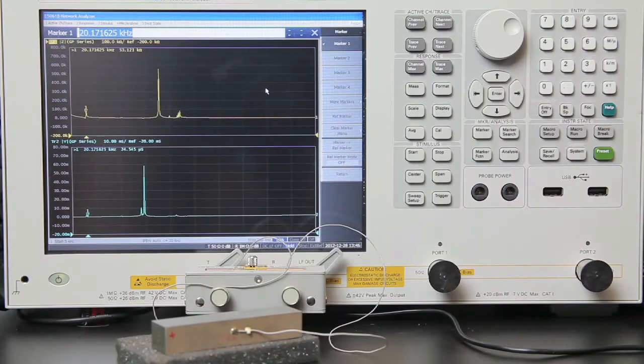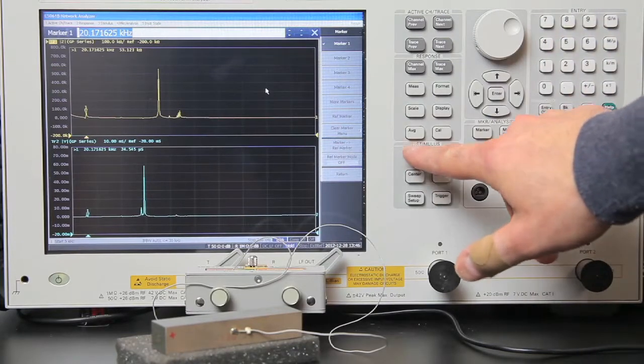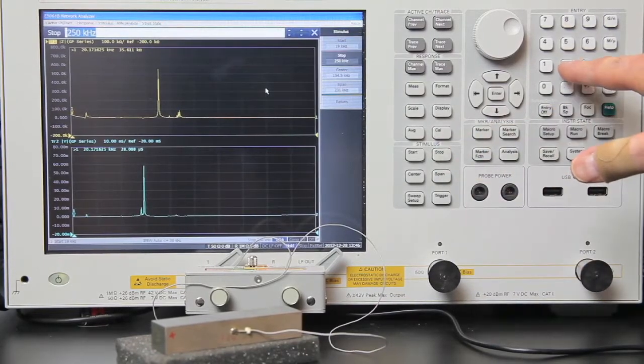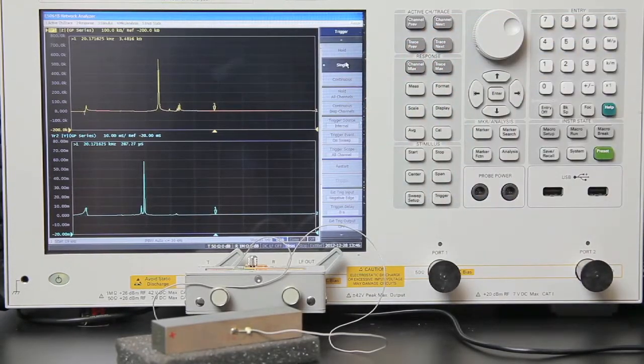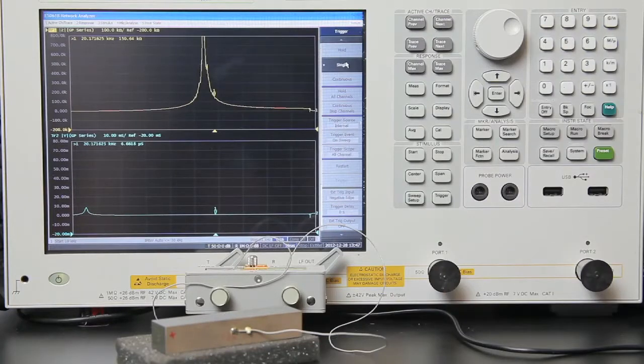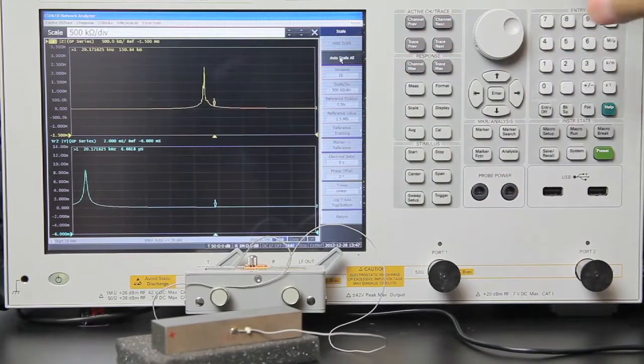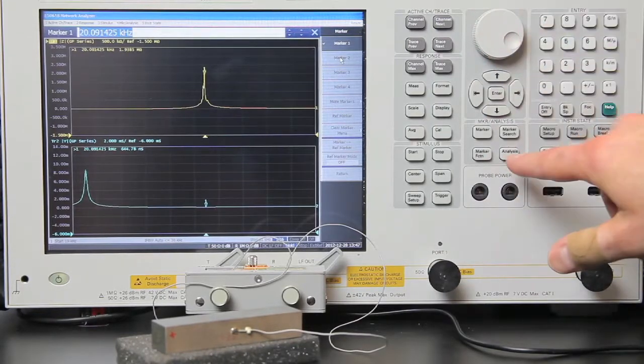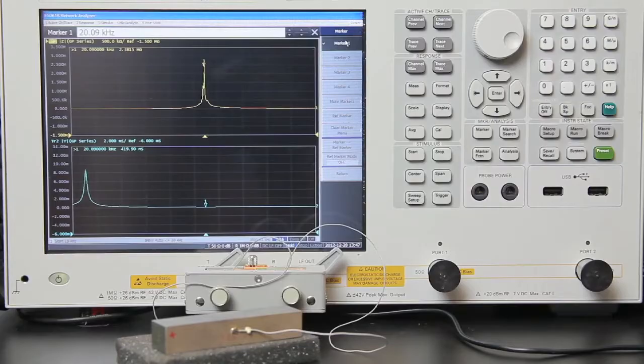To get better data around this first impedance peak, we can do a narrower sweep. This peak is at 20 kHz, so I'm going to pick a start frequency of 19 kHz and a stop frequency of 21 kHz, and I'll go ahead and do a single sweep. Once the sweep is done, I'll do auto scale all. Here is our first impedance peak. I'll do a marker search maximum — we're at 20.09 kHz.